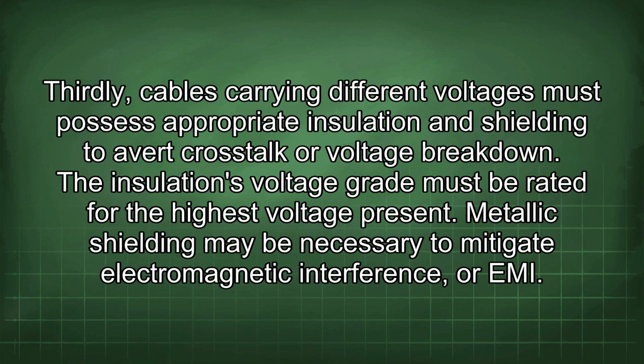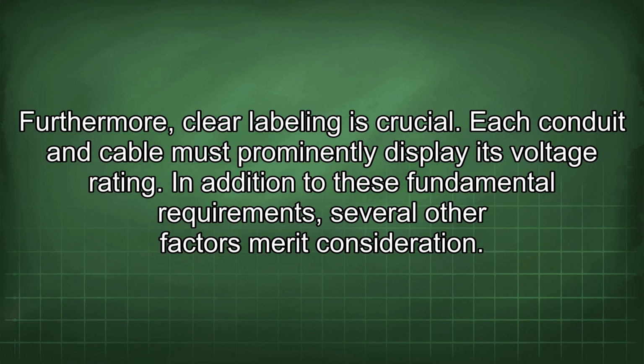Thirdly, cables carrying different voltages must possess appropriate insulation and shielding to avert crosstalk or voltage breakdown. The insulation's voltage grade must be rated for the highest voltage present. Metallic shielding may be necessary to mitigate electromagnetic interference, or EMI. Furthermore, clear labeling is crucial. Each conduit and cable must prominently display its voltage rating.